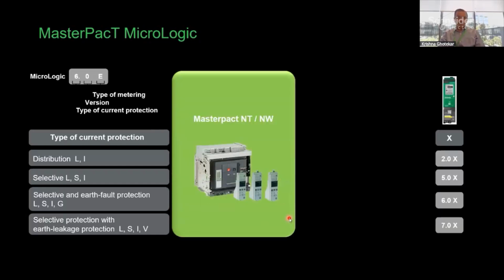Whereas in MTZ X, if you have used it or quoted it in some project, it's called MicroLogic X. So there is only one version of a trip unit. As I said, it's with higher features targeting critical applications. So it comes with 2X, 5X, 6X, and 7X. So 2, 5, 6, 7 are the protection part, and X stands for the metering type. In MicroLogic X of MTZ, it comes with current, voltage, power, energy, frequency, and THD parameters. So total harmonic distortion is embedded. Of course, you can add individual harmonics and other features with an add-on digital module or a software module to the trip unit.